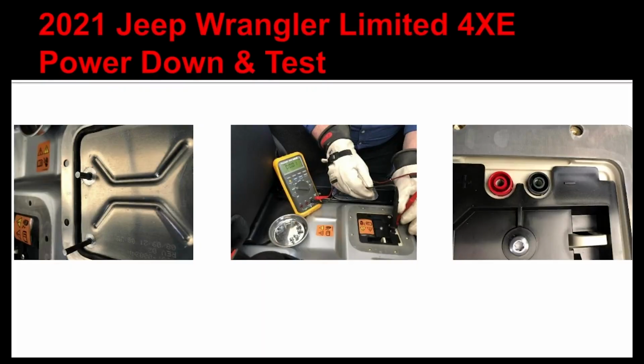But here's the anomaly: when you pull that cover off, it's one more HVIL. We have 2 dowel pins, spot welded metal pins of different lengths, and you remove the tamper-proof torque screws to pull this cover off. These pins engage some circuits in here, not live electrical circuits, but switch circuits, sometimes called trip switches.